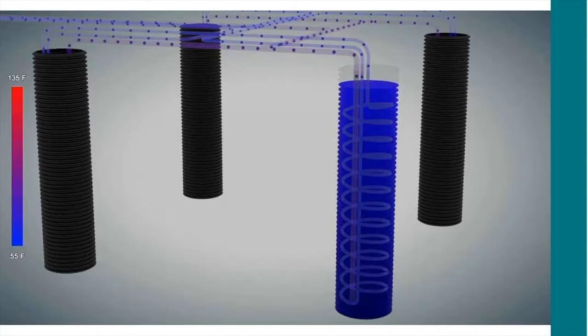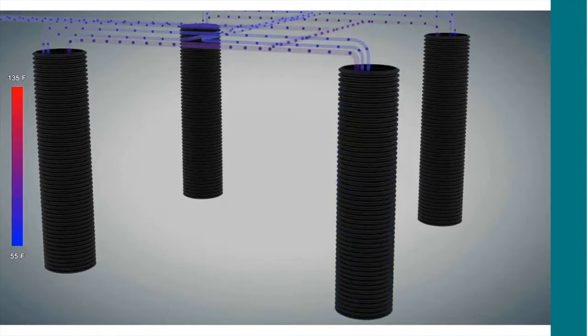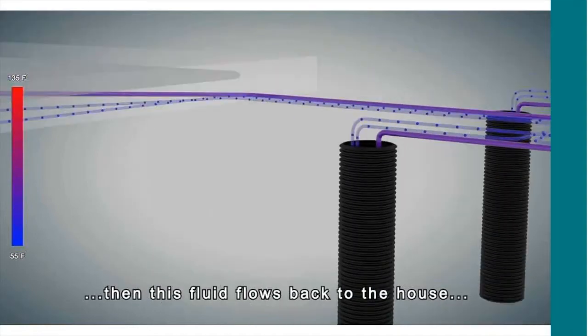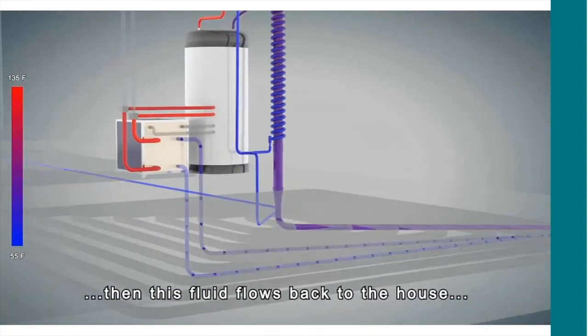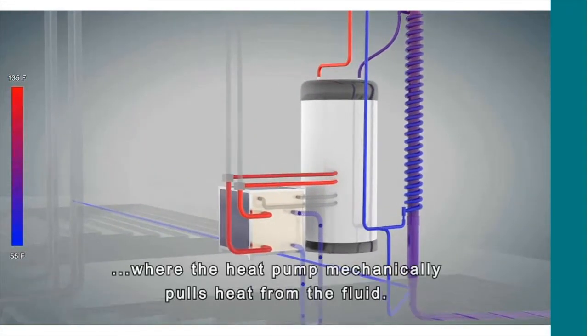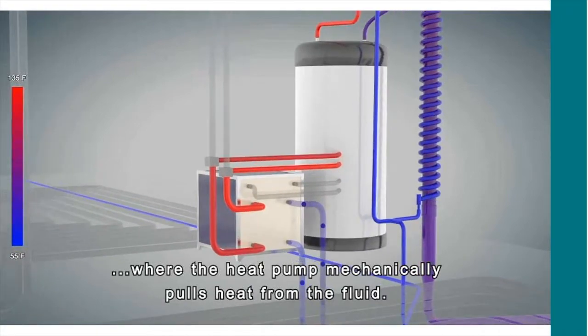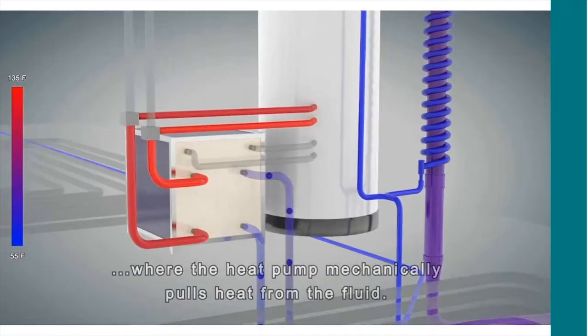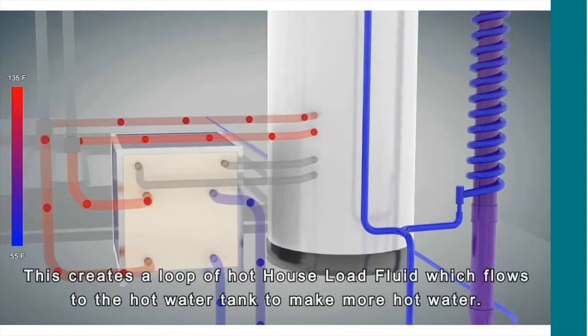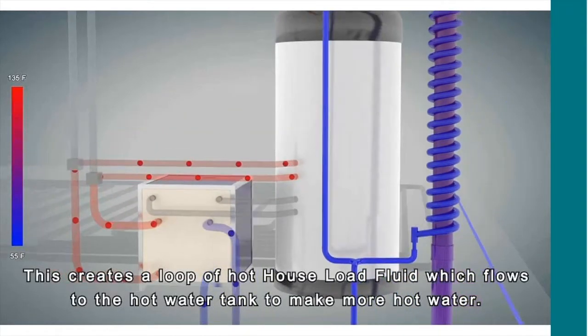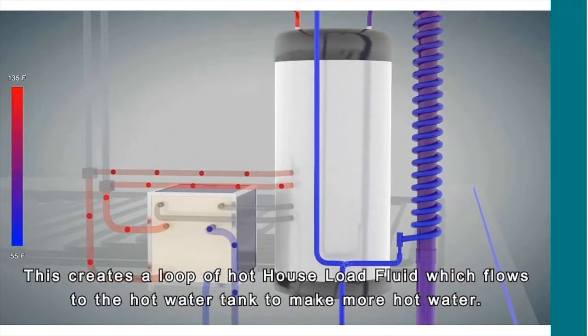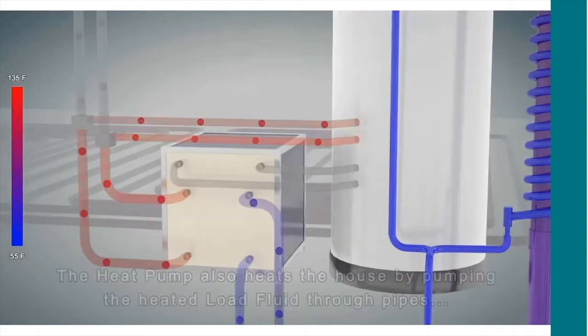In the process, we've got the coils, the source side coil, so we can exchange energy. We can pull the nice preheated fluid, take its energy out, send it back to the heat pump, and then mechanically compress and make more hot water, sending that back into the hot water tank. So we do actually recover some of that heat from the gray water.